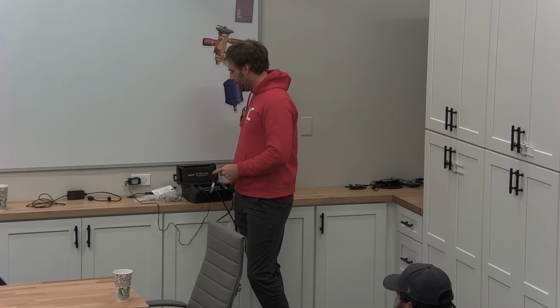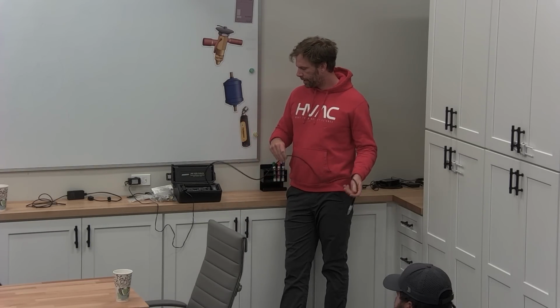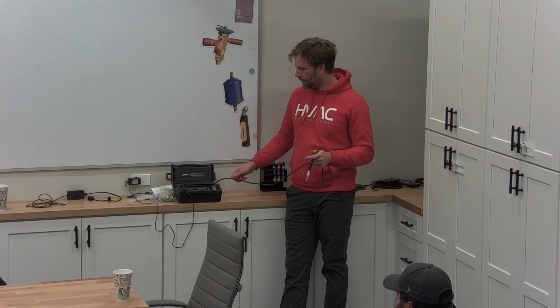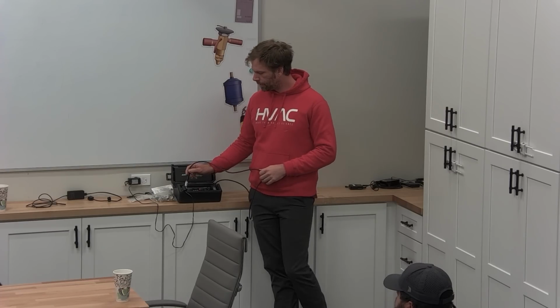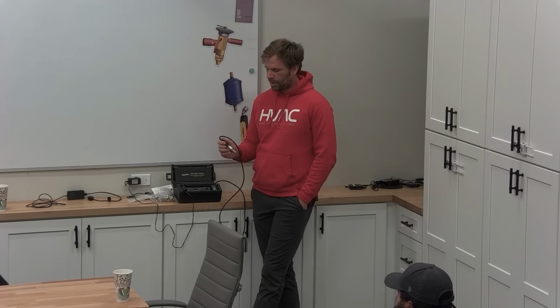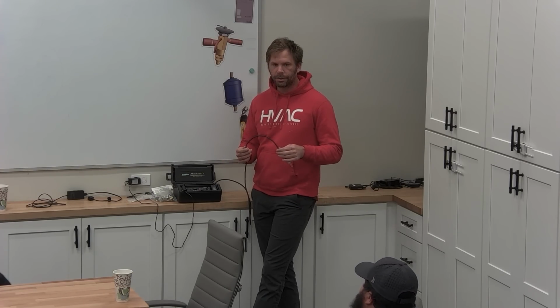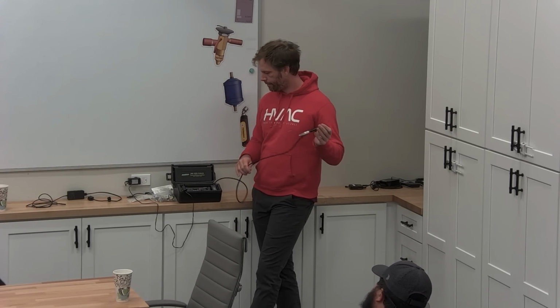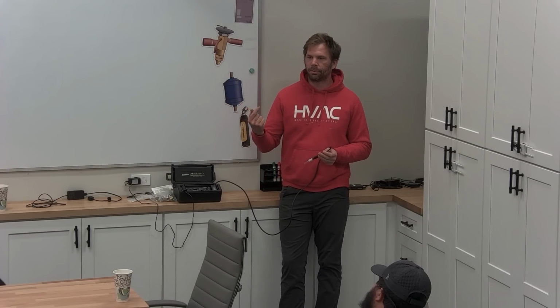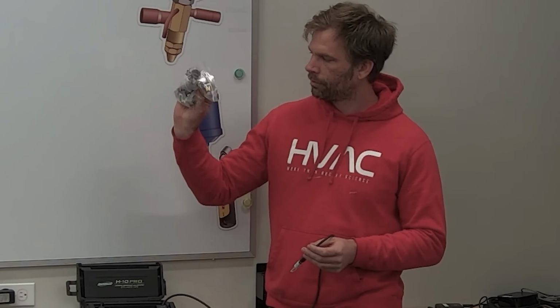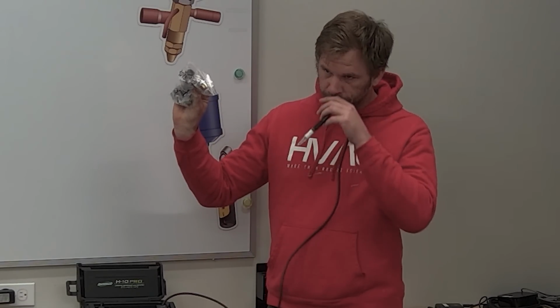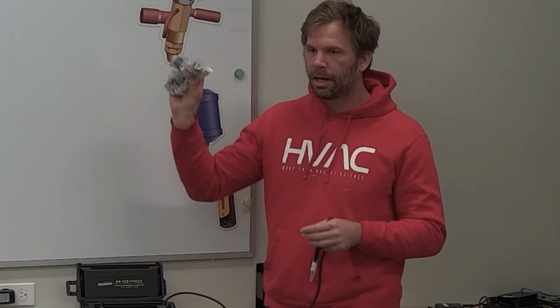Okay, other than the sensor going out because of water or because of use, and using your calibration, you can find out that this actually isn't going off the way it used to. Maybe I need a new sensor. The other thing that can fail is you have a leak somewhere in your hose, so it's not pulling air directly in through here, and that could be all the way back to the connection on the board, or the blower pump, the air pump on the, I don't know why I'm calling it a blower.